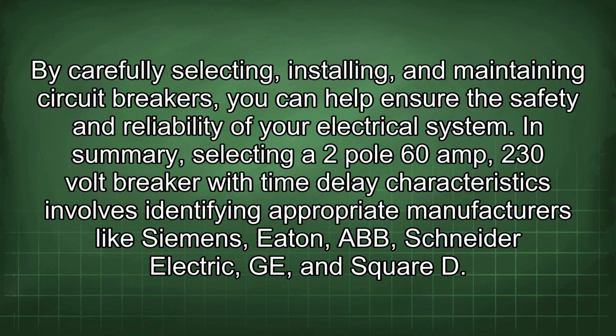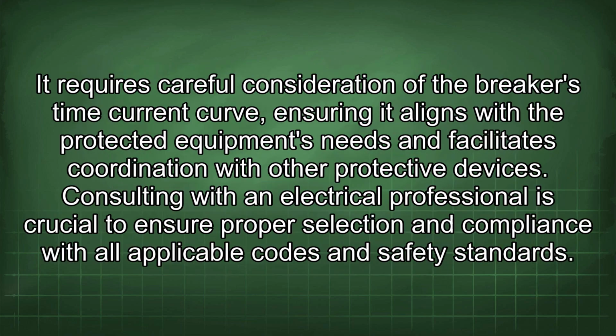In summary, selecting a 2-pole 60-amp, 230-volt breaker with time delay characteristics involves identifying appropriate manufacturers like Siemens, Eaton, Schneider Electric, GE, and Square D. It requires careful consideration of the breaker's time current curve, ensuring it aligns with the protected equipment's needs and facilitates coordination with other protective devices. Consulting with an electrical professional is crucial to ensure proper selection and compliance with all applicable codes and safety standards.